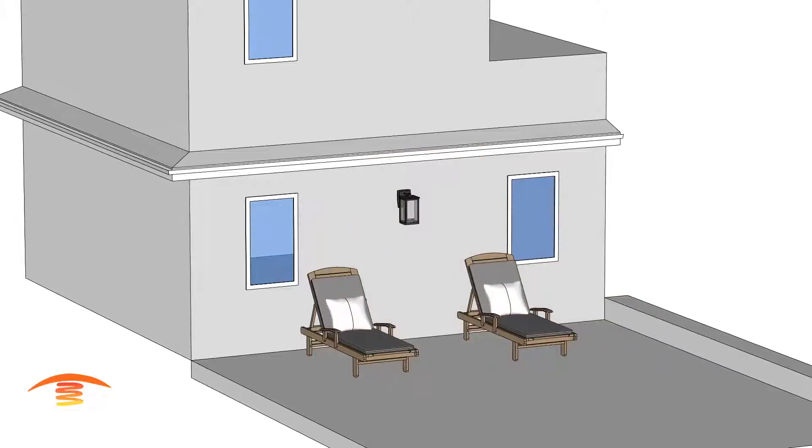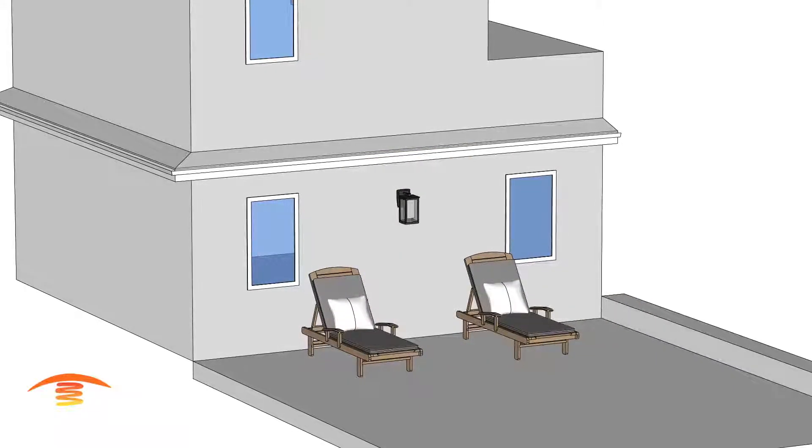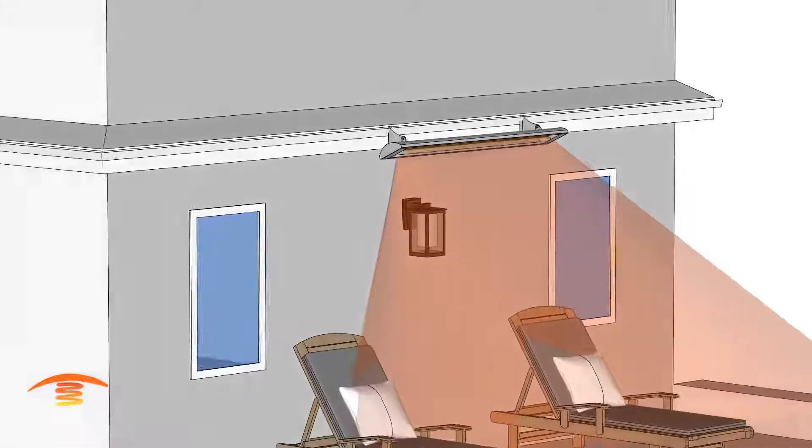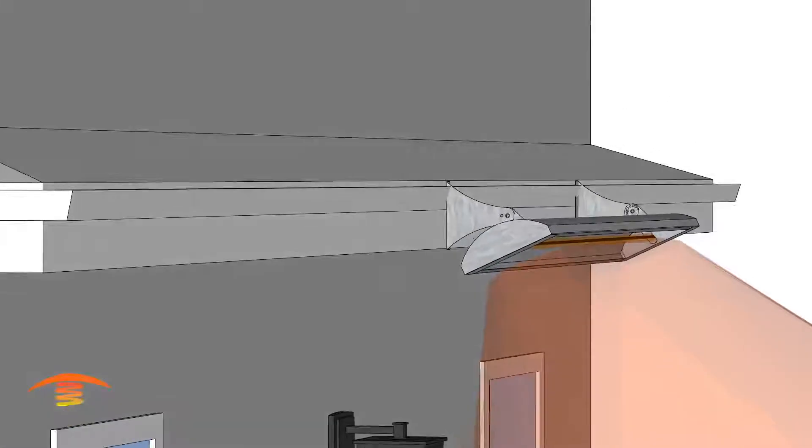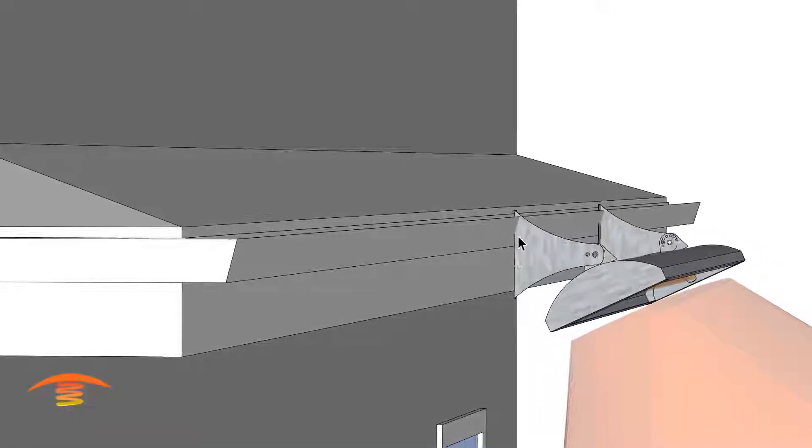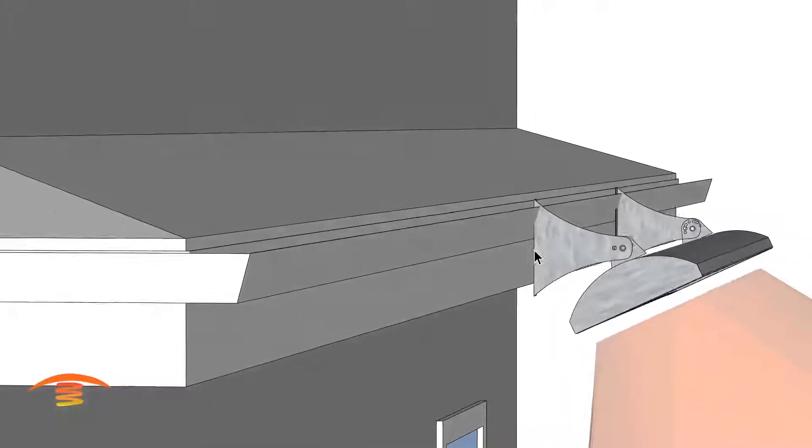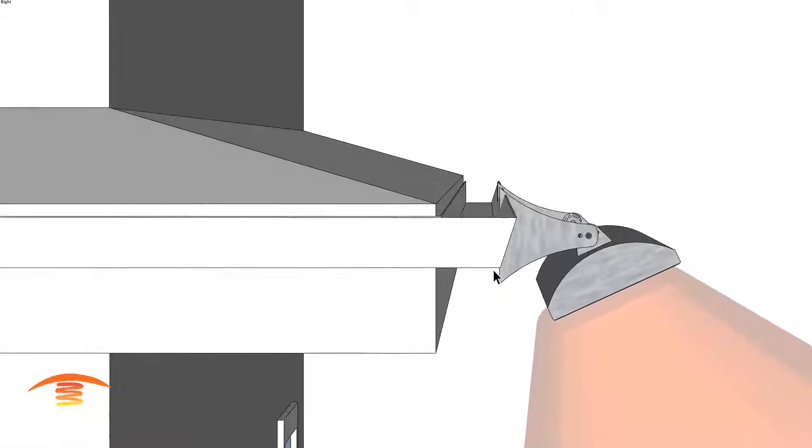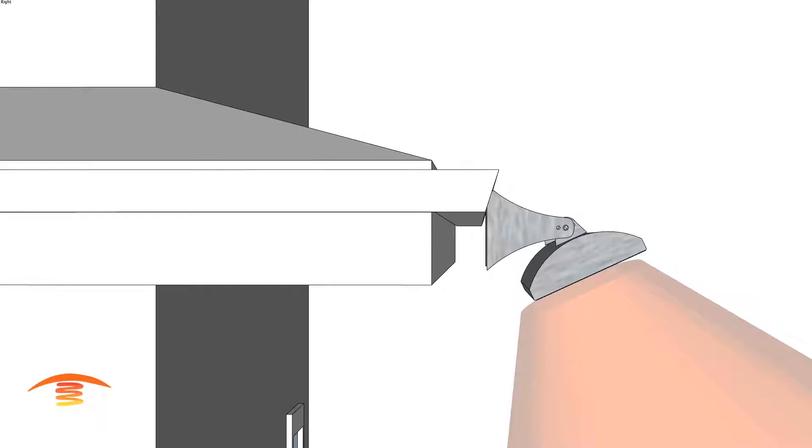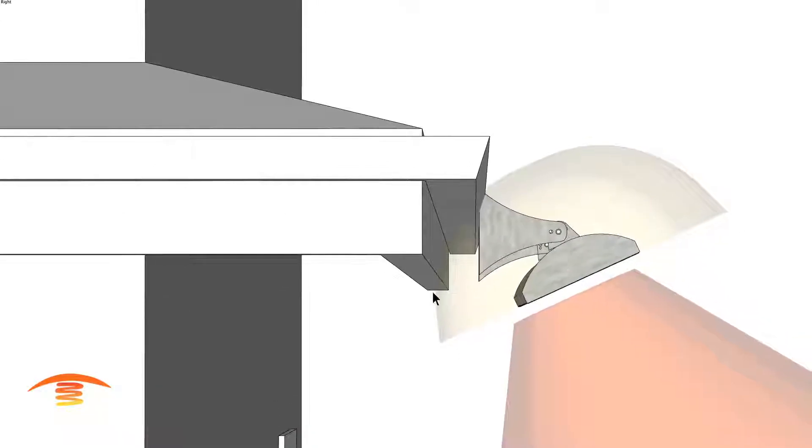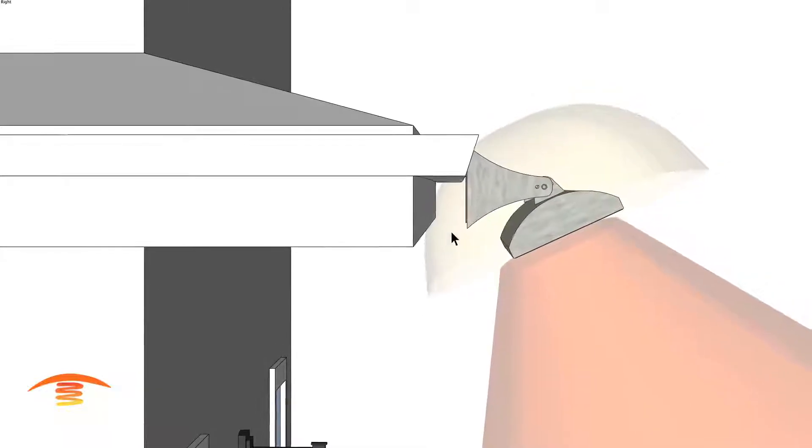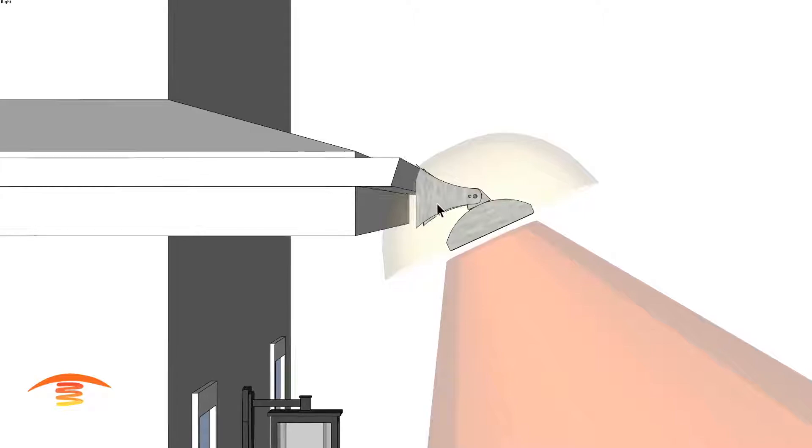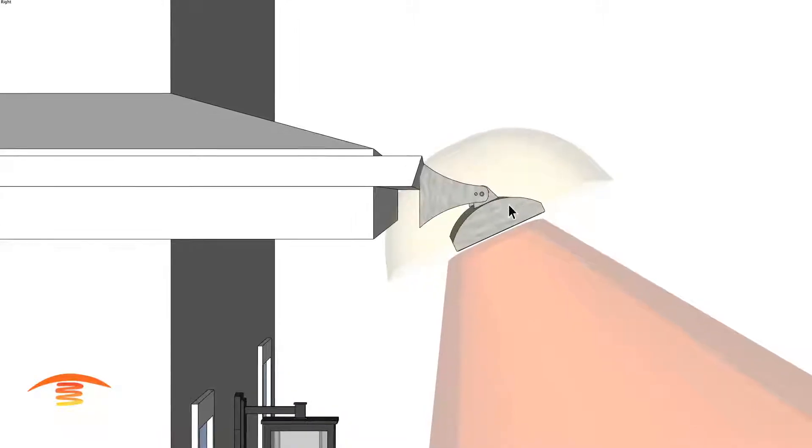So the other option would be the C series heater. The C series heater has a different bracket. You can see that my bracket here is expanding across the whole entire area here, but you can also see I had to push this out as well for the exact same reasons. That same reason would be the clearance around the heater. And so I need that six inches back here and pushing the heater out and I just pushed the bracket with it this time.